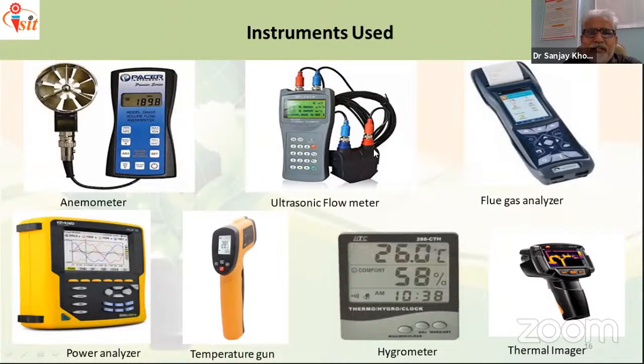The second one is the ultrasonic flow meter. This ultrasonic flow meter is a non-contact type of flow meter. With it we can measure the flow of water or other fluids, such as milk. This is also most of the time essential while doing a water audit. Suppose the pump is 10 HP and has some specification, design or operating parameter for how much flow it should have. But actually nobody measures the flow of water through the pipeline, and because of rusting, corrosion and many other issues, there is a drop in the discharge of the pump. Pumps are getting old also, and the motor has issues. So with the help of the ultrasonic flow meter, we can actually measure the flow of the water.